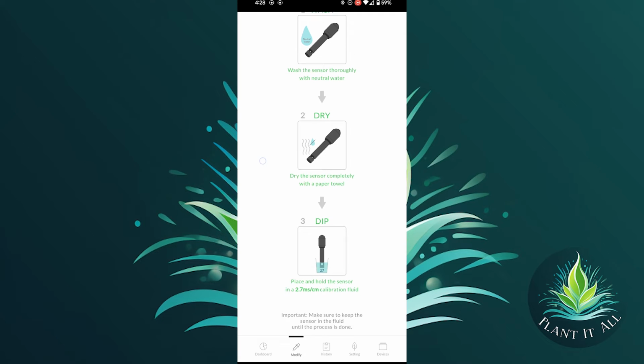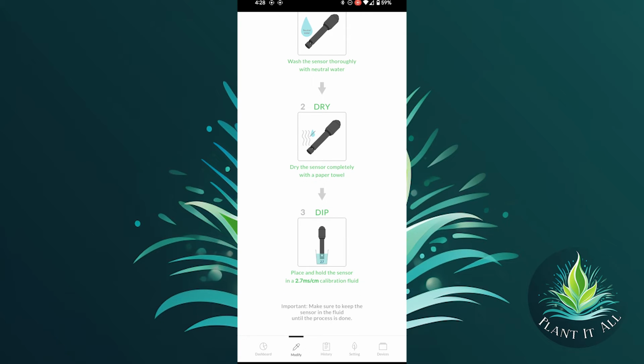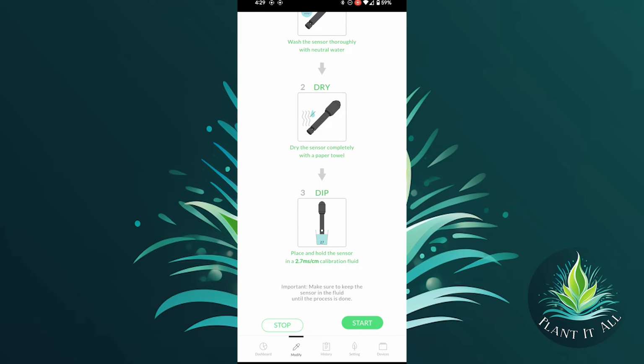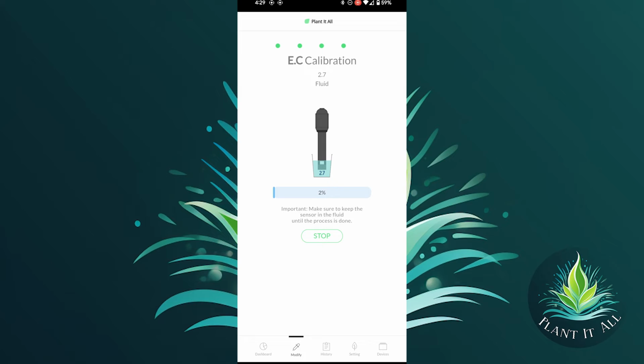And remember, jiggle around the probe head. Make sure that you haven't gotten any air pockets on there that are going to prevent the solution from coming into direct contact with the probe itself. Once you're all set, go ahead and hit the start button. Okay, same screen as before. We're just going to let that little bar fill up, keep the probe properly submerged, and you're going to be good to go.